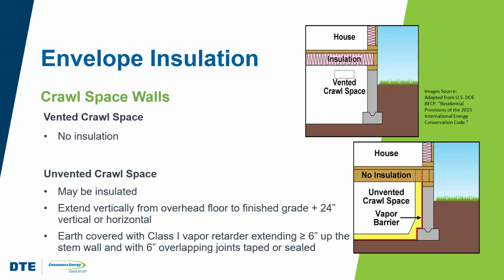Now, unvented crawl spaces are actually ventilated. Their ventilation rate is 1 CFM for every 50 square feet of crawl space area. And that ventilation can either be by mechanical exhaust or it could be by a supply of conditioned air actually from the home.